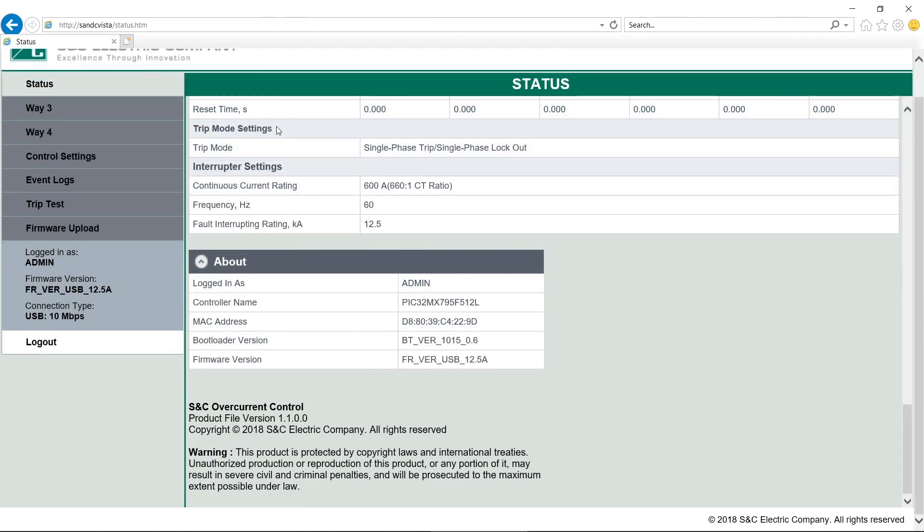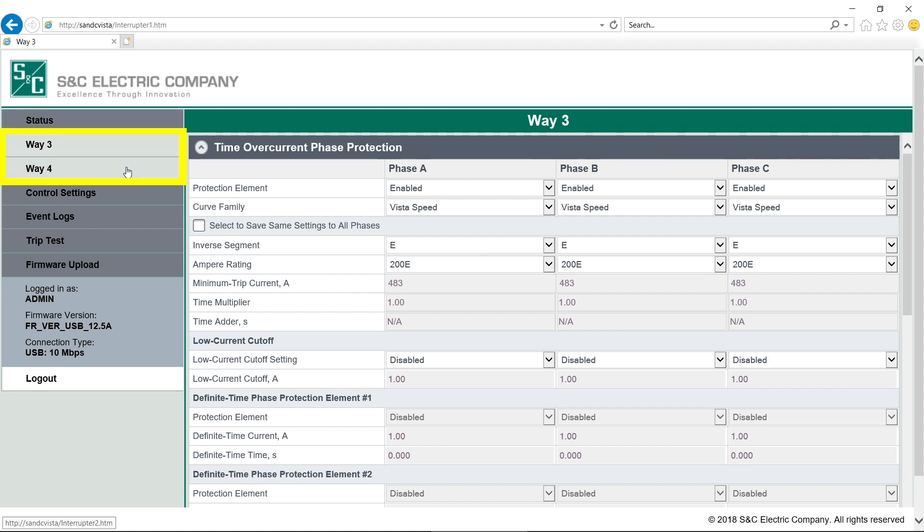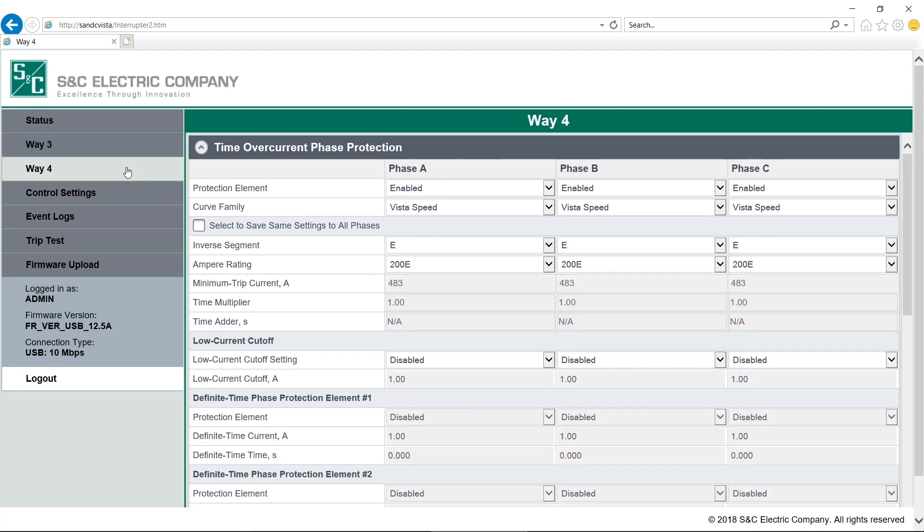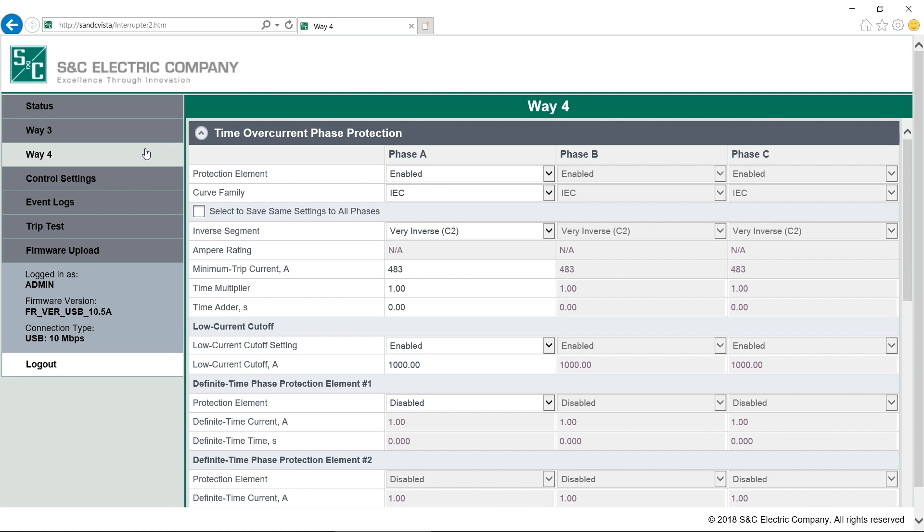Below the Status tab, we have controls for each interrupter. The interrupter IDs are programmed at the factory to match the WAY designation of the switchgear. So here we have Way 3 and Way 4. We can rename these however we want as well. If you are in admin or user mode, you can program the protective settings from here. You can see all the different fields you can set. There's a lot of information in the written instructions on all of these attributes. You should be very familiar with that document before you try and program the device. All WAYs are set at 200E as factory default protective settings. I'll show you some basics of programming in a bit, but first, let's move on to the Control Settings tab.